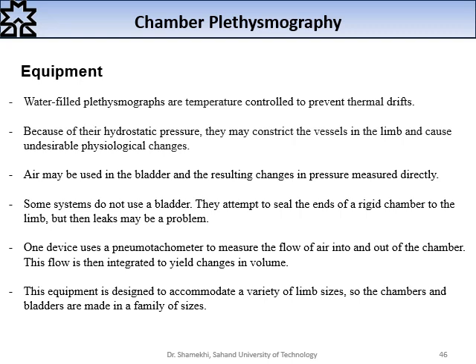One device uses a pneumotachometer to measure the flow of air into and out of the chamber. This flow is then integrated to yield change in volume. This equipment is designed to accommodate a variety of limb sizes, so the chambers and bladders are made in a family of sizes. We should select an appropriate bladder size.